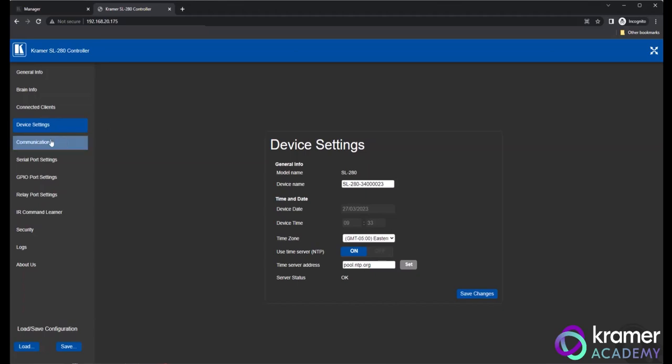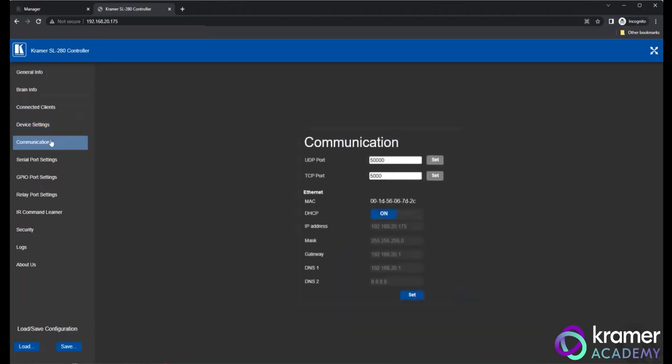When you select Communication from the menu on the left, you'll gain access to the SL hardware's network details. The default networking ports for control of the SL are UDP-50,000 and TCP-5000. Within the Ethernet field, we can set the necessary static IP information for the hardware. The default setting of the SL is DHCP.